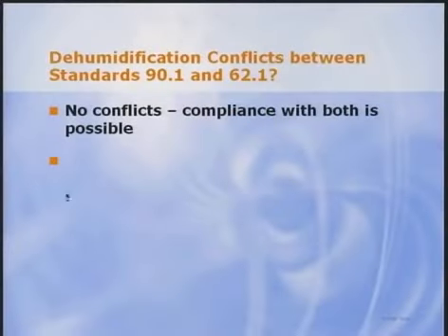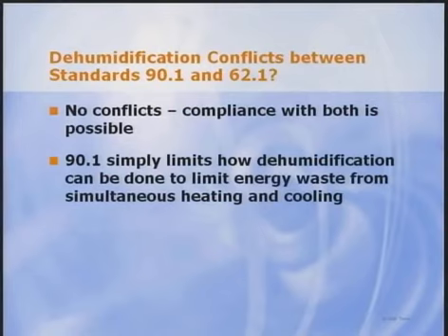So Steve, do you see any conflicts between ASHRAE standard 62.1 and 90.1 with respect to dehumidification? No, I don't. Compliance with both standards is possible with the same system design. Standard 90.1 limits how dehumidification can be done to reduce energy waste, but there are many exceptions to the simultaneous heating and cooling limitation, leaving many options for designers. Compliance is actually very easy. Here are a few compliance options designers should consider.